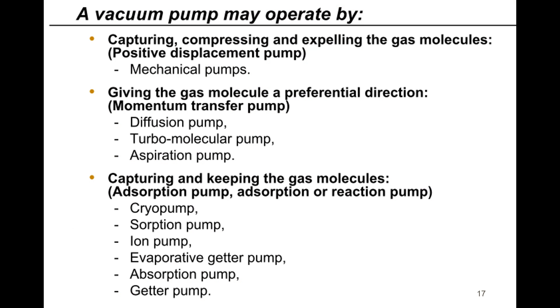The first general principle: a vacuum pump may be operated by capturing, compressing, and expelling gas molecules — that is called a positive displacement pump. A good example is the mechanical pump. The second working principle involves giving gas molecules directional momentum — that is the momentum transfer pump. Examples include the diffusion pump, turbo molecular pump, and aspiration pump.